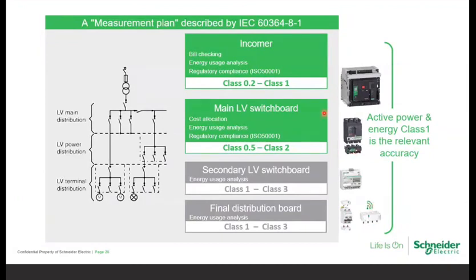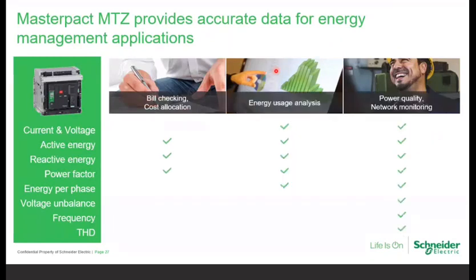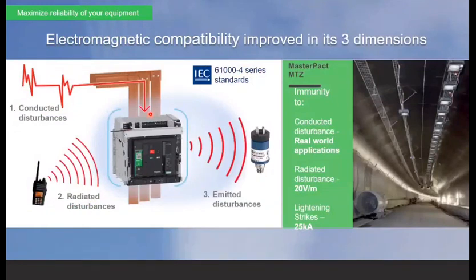This is the reason why MTZ is complying to IEC 60364-8, ISO 50001 and IEC 61557-12. So these are a few examples. For what application can you use the MasterPact MTZ ACB? Be it bill checking or cost allocation, energy usage analysis, power quality or network monitoring. You can use the MTZ ACB for all these applications in your installation, and it is very well recommended and complies with the standard requirements. So we have strengthened our core by improving the class of metering accuracy, by providing the inbuilt accuracy throughout the performance range. Then we have an MTZ ACB with improved EMC compliance.